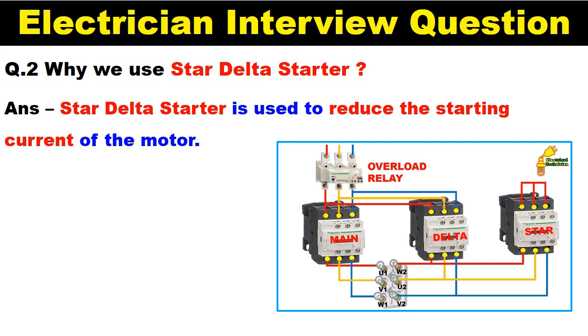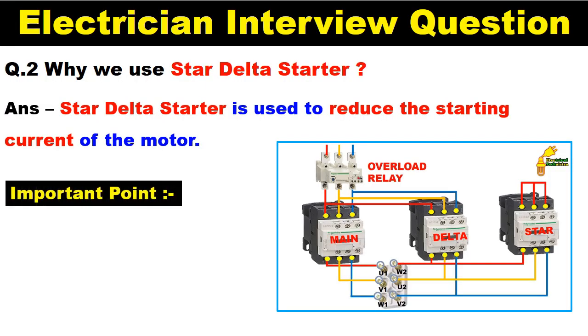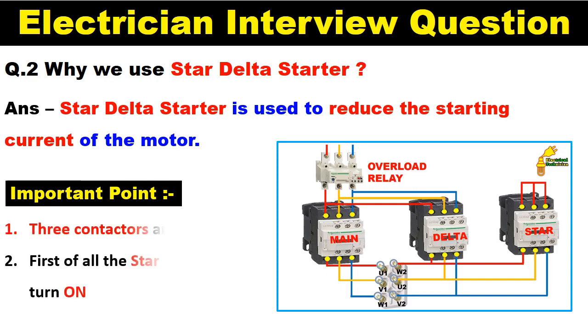You must also know some more things regarding this. In a star delta starter, three contactors are used: one main contactor, one delta contactor, and one star contactor. When we turn on the motor, first of all the star contactor gets turned on.